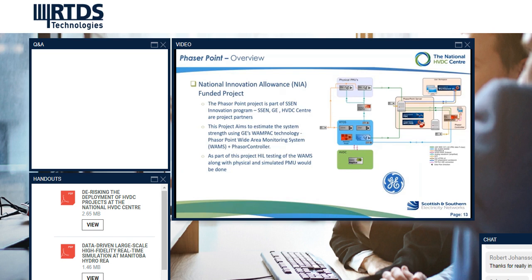Mainly the PMUs would communicate with the Phasor Point wide area controller using IEEE C37.118 protocol, while the phasor controller communicates with the RTDS using IEC 61850 protocol. And also you can see that all the components are being time synchronized using a centralized GPS clock using various time synchronizing protocols.